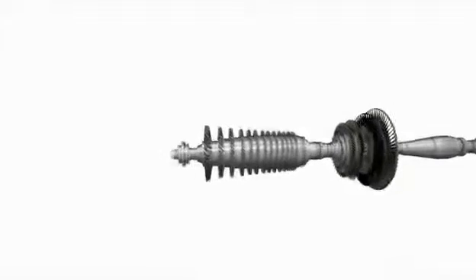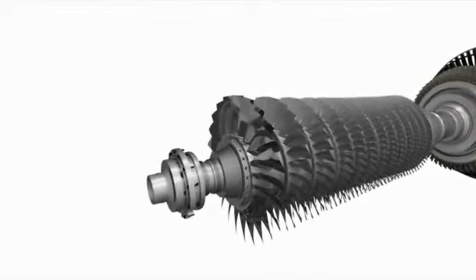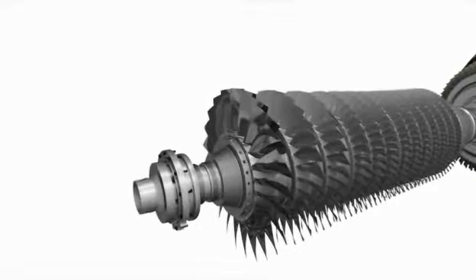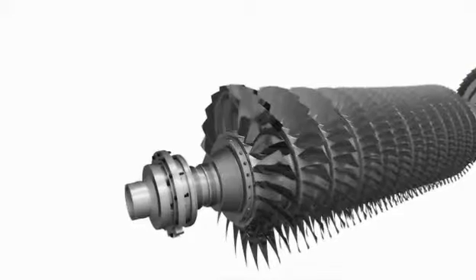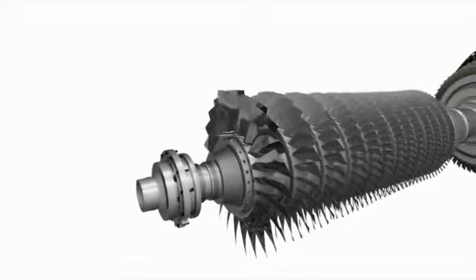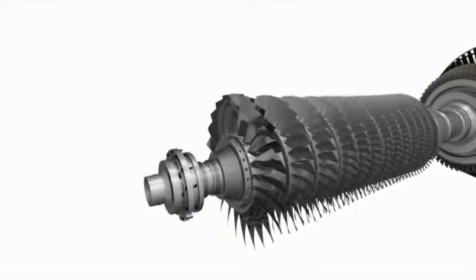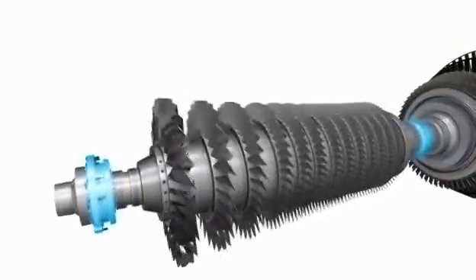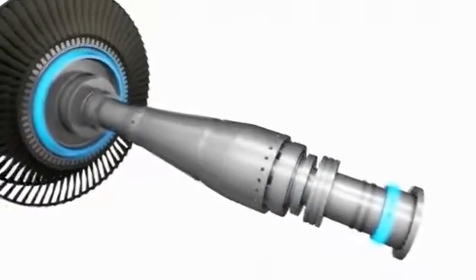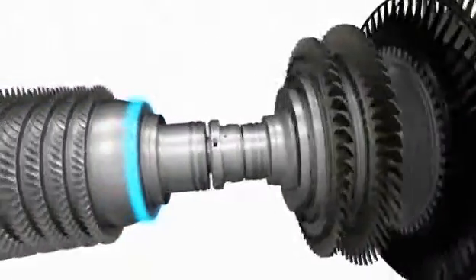The rotors incorporate the heritage of Siemens Electron Beam Welding. The single rigid compressor rotor body ensures reliable, stable and uniform run-up in hot or cold conditions. Axial blade attachment grooves allow blade replacement without rotor removal. The turbine discs are bolted to the compressor rotor and supported with mineral oil lubricated long-life tilting pad bearings. The balancing planes allow field balancing on-site without disassembly. Even in the early engineering phase, we can design in future maintainability and serviceability.